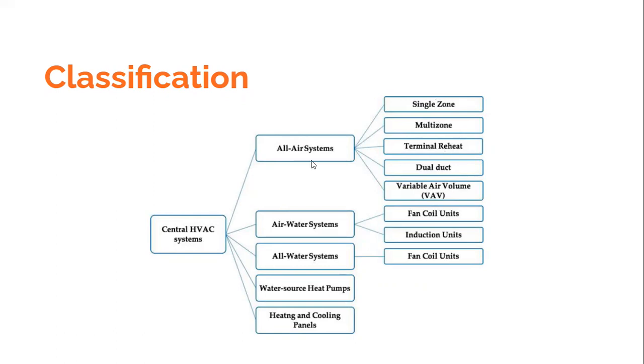So all this can be clubbed together into a category called all air systems. So what do all air systems mean? You have an air handling unit, and the air handling unit would supply the conditioned air to the space to be cooled, and then the air would be carried back, returned back to the air handling unit. So this is generally the layout of all air systems. There is no chilled water used in these systems, or hot water used in these systems. So that is all air systems.